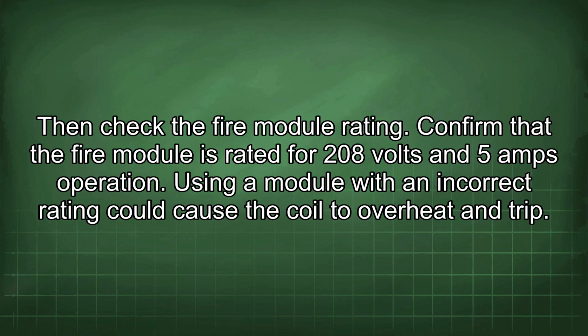Then check the fire module rating. Confirm that the fire module is rated for 208 volts on 5 amps operation. Using a module with an incorrect rating could cause a coil to overheat and trip.